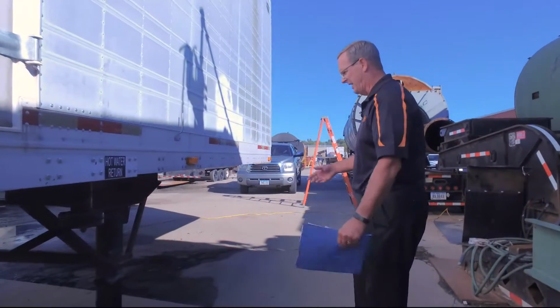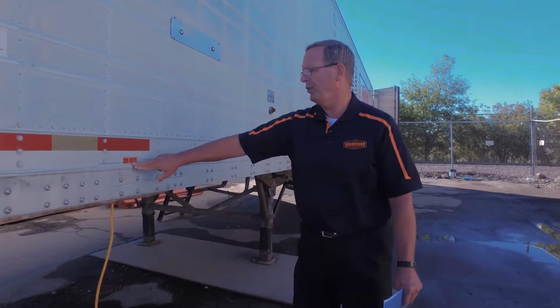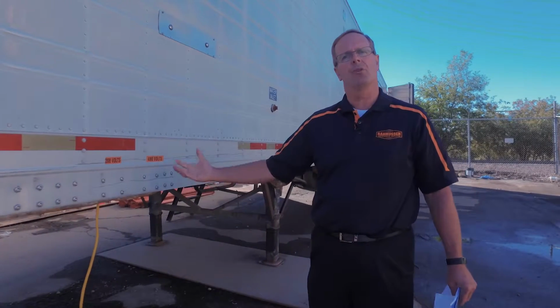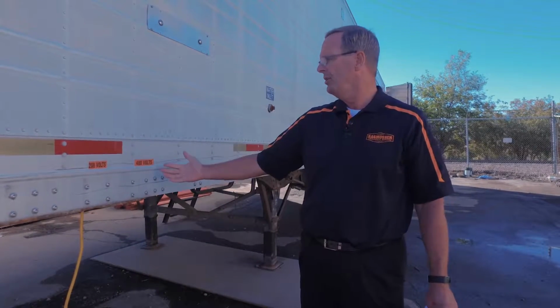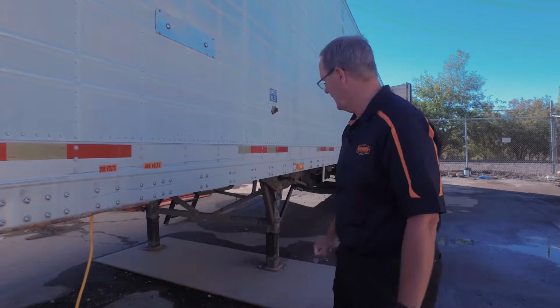We don't have to cut any holes or go through the thing. Over on this side we have our electrical connections. As you can see, there's a 208 volt connection or a 480 volt connection. All goes in basically through the same portal and enables us to go to our transformer and all of our switch gear inside. So it's pretty easy to hook up, whether we're 208 three-phase or 480, we've got the transformer inside and a single point connection.